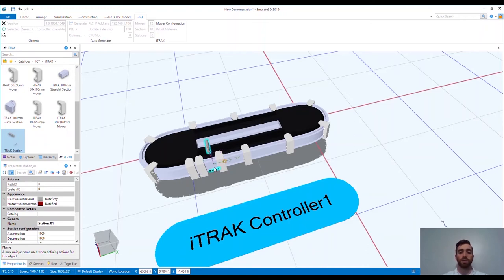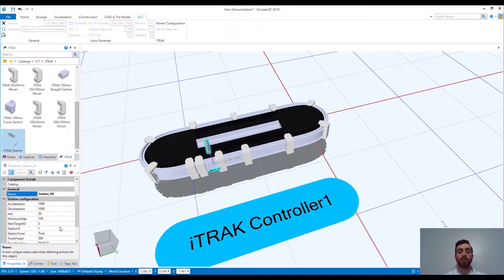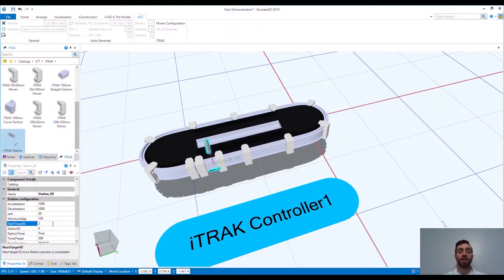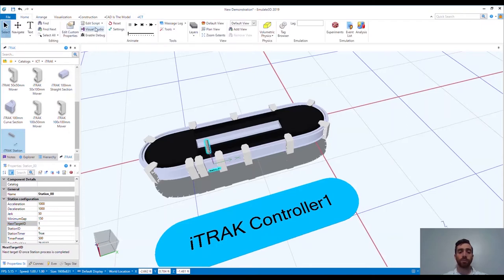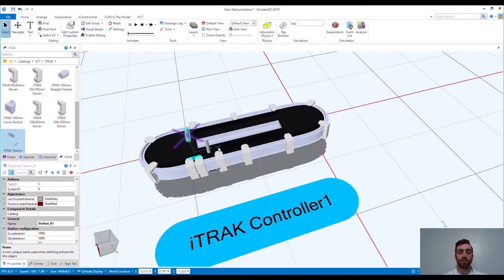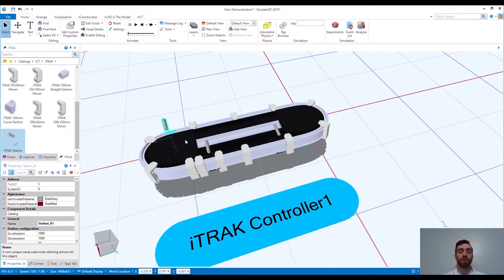What we want to do next for some base controls of the system is to add stations to the track. These stations pair with the ICT libraries in Application Code Manager, leveraging an AOI for an awesome control starting point. Movers will move from station to station, leaving the station they are at once the station complete command is triggered.